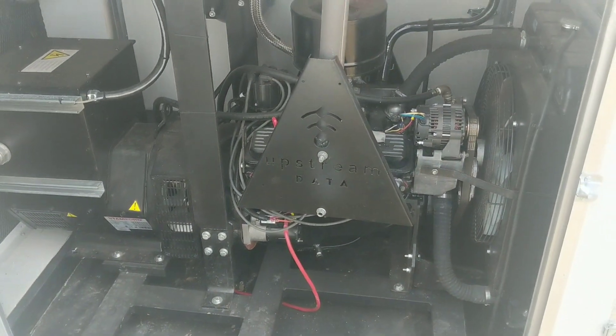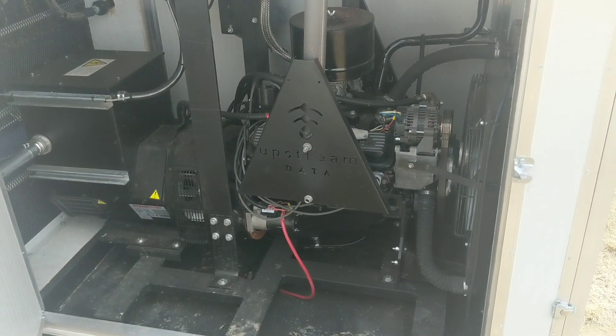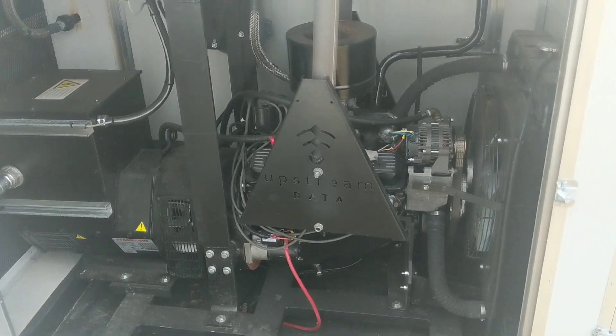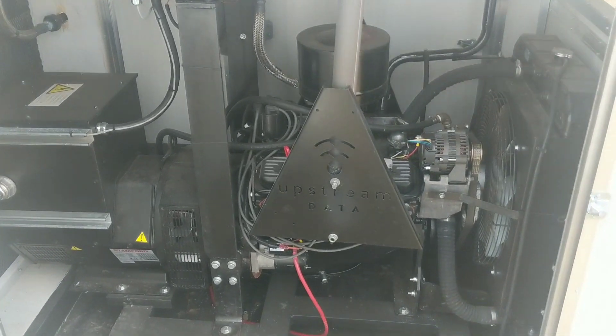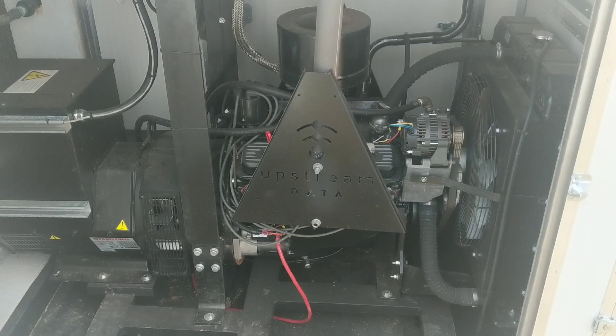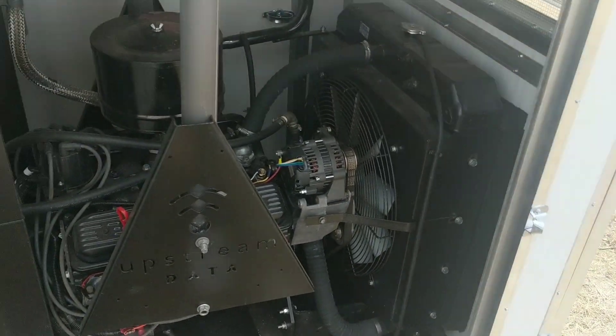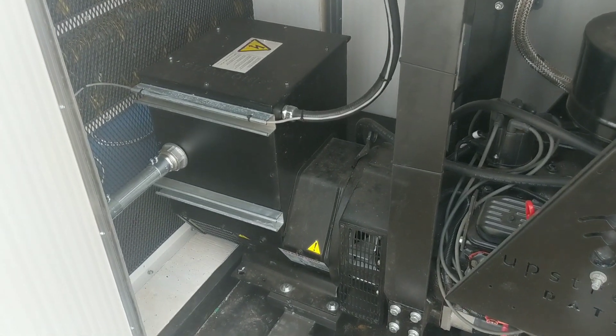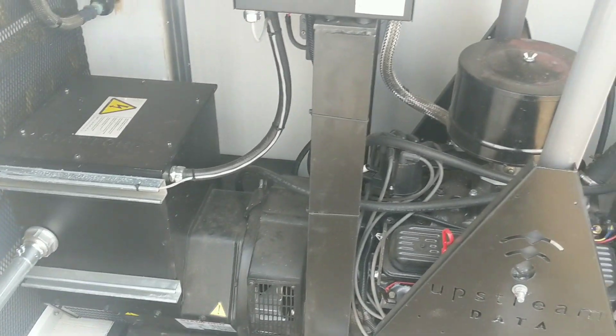We assemble the engine in-house in the genset. This is a 5.7 liter Vortec, like a GM small block, natural gas aspirated engine. We have an oversized radiator, and about a 50 kilowatt generator end. This happens to be a Stamford model, although we offer a few different options.